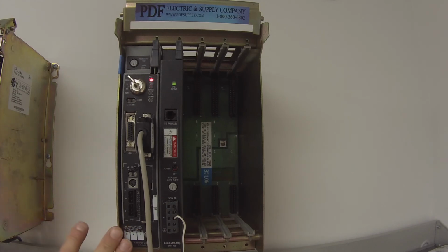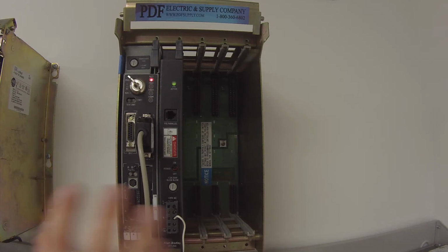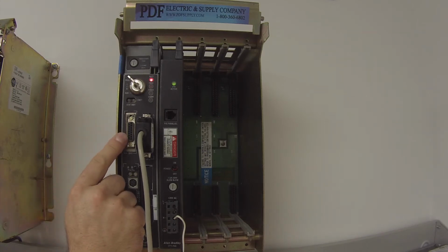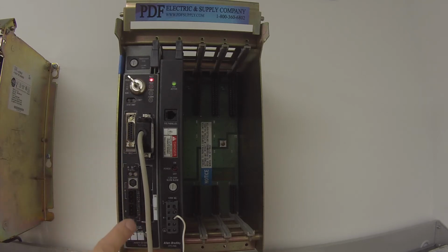So now would be a good time to tell you that this processor I have here has a battery that's been tested good. I say this particularly on the Ethernet modules. Of course, you should always have a good tested battery in these processors. But in the instance that you remove the processor and you're testing it solely, if you've configured an IP address, sometimes you need to power cycle in order for that IP address to take. So it would be good to have a battery that's in good working order, or actually a must. So just make sure that that's working properly.